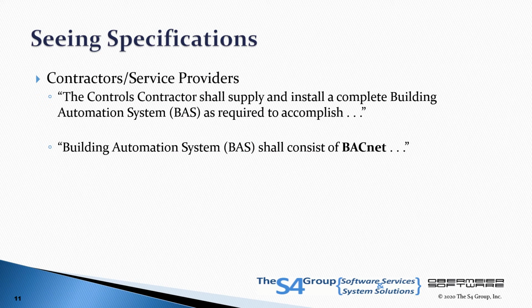The first requirement in any specification seeking to create a smart building should be the use of the BACnet protocol. This ensures interoperability and maximum competition between manufacturers. Then, the specification should address the functionality or sequence of operations that must be delivered by each device or value-added application.